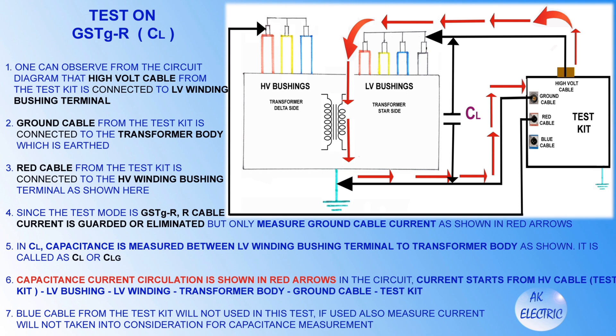In this slide we will see the test on GST-GR mode for CL type. The high-voltage cable from the test kit is connected to the LV winding bushing terminal, and the ground cable is connected to the earthed transformer body. The red cable is connected to the HV winding bushing terminal. Since the test mode is GST-GR, red cable current is guarded or eliminated — only ground cable current is measured. In CL type, capacitance is measured between the LV winding bushing terminal and the transformer body, called CL or CLG. Current starts from the HV cable in the test kit, then to LV bushing, LV winding, transformer body, ground cable, and ends in the test kit. The blue cable from the test kit is not used; if used, its current will not be taken into consideration for capacitance measurement.